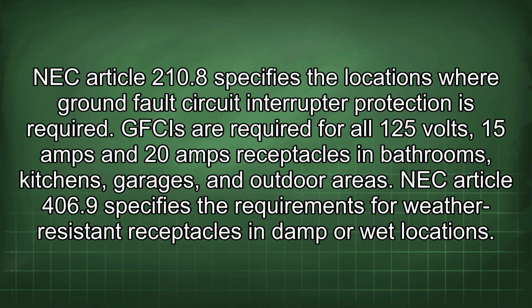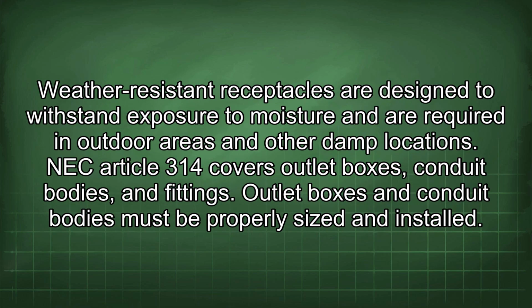NEC Article 210.8 specifies the locations where ground fault circuit interrupter protection is required. GFCIs are required for all 125 volt, 15 amp and 20 amp receptacles in bathrooms, kitchens, garages, and outdoor areas. NEC Article 406.9 specifies the requirements for weather-resistant receptacles in damp or wet locations. Weather-resistant receptacles are designed to withstand exposure to moisture and are required in outdoor areas and other damp locations.